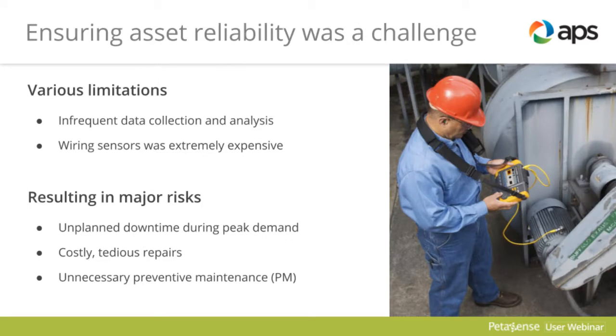Reliability was foremost in our mind for these units with the amount of work they're now getting. The other problem with being so far away from the valley and running basically during those shoulder hours is there's typically not people down there during those times the units are running. So getting vibration data particularly, you need the unit running, and if no one's there, you can't get the data.